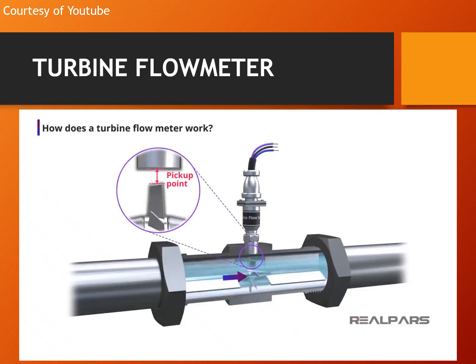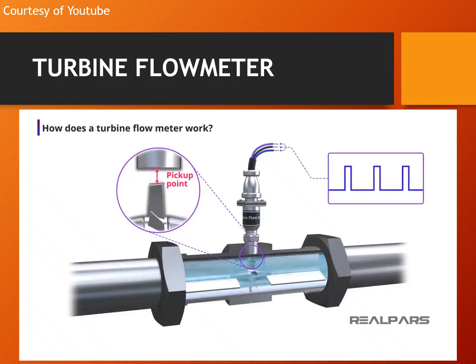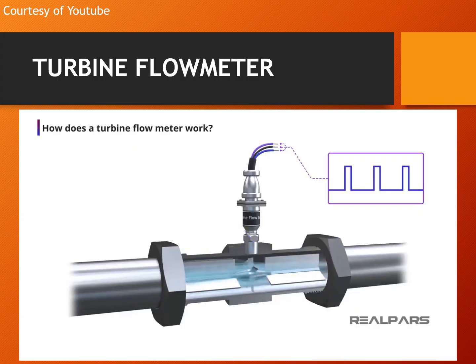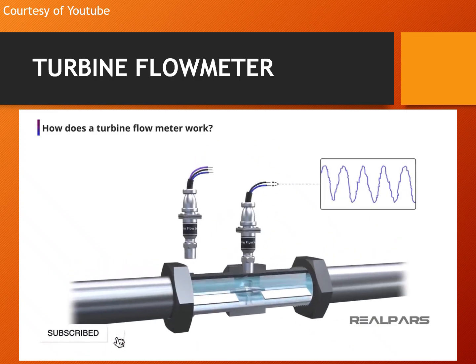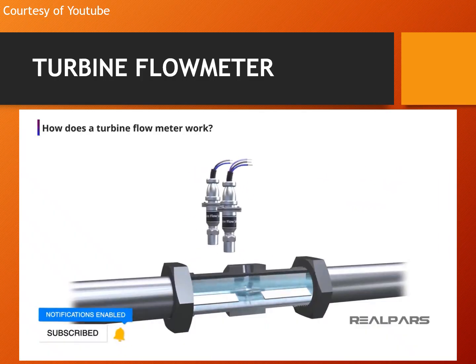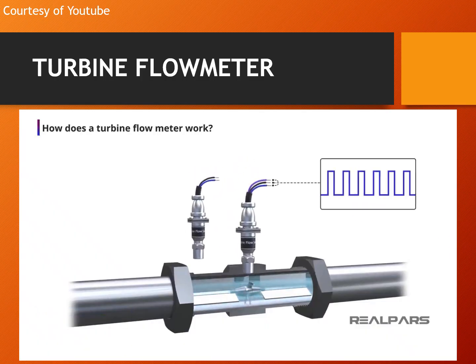As the rotor spins, the passage of each rotor blade past a pickup point will generate an electrical pulse. The electrical pulses are created in different ways, depending upon the rotor blades themselves and the pickup unit characteristics. In most turbine flow meters, magnets are fitted to the blades, and a magnetic pickup sensor is used to create the pulses. The higher the rate of flow, the faster the rotor turns, and the greater the number of pulses. The shape and the voltage level of the generated pulses depend entirely upon the type of pickup unit used.